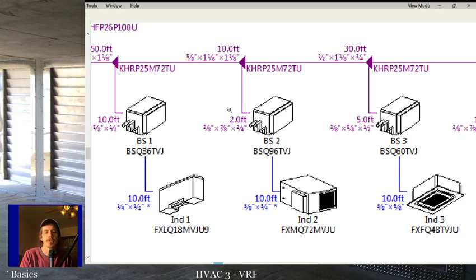Try and think of refrigerant in a VRF system the way you think about duct. You know what I mean? With duct it's real easy to picture the air if you go a 90 then a 90, or if you go a branch and then a 90 immediately, right? Then you're going to have turbulent flow in that 90 and you're going to get less airflow than if you used a nice high efficiency takeoff and then ran smoothly after that branch.